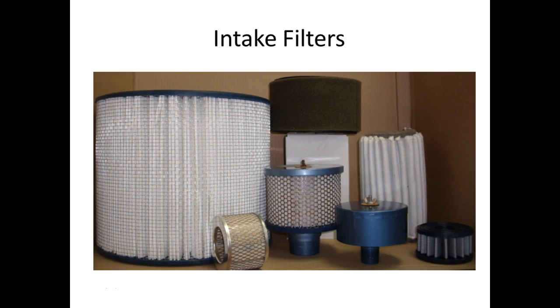Intake filters, you need to filter your air really well. You know why? Especially on reciprocating compressors, you get contamination in your cylinders. Any abrasion can cause your rings and everything to wear out, which is real bad. You need to keep your intake filter. I've seen people run lawnmowers without them, and then they wonder why they start smoking after a while.